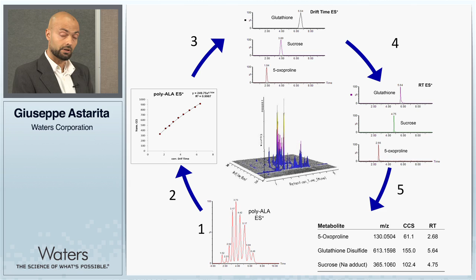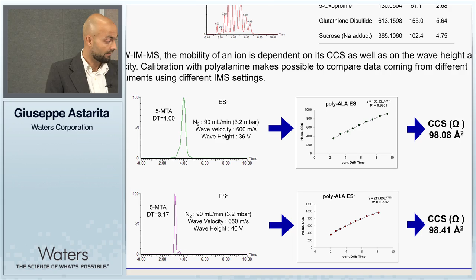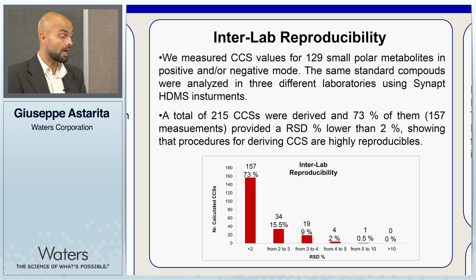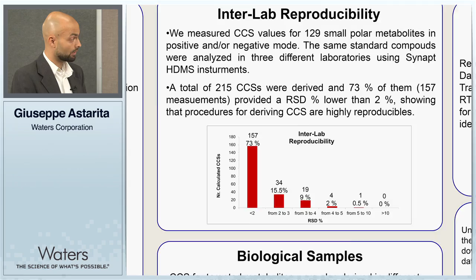The use of a calibration curve allowed us to use different settings for ion mobility for collision cross-section calculation. In this example, we show that we could use different wave velocity and wave heights to obtain 2 different drift times for the same metabolites, which, however, after the calibration curve, led to very similar collision cross-section values. Again, the use of calibration with polyalanine allowed us to use different instruments based in different laboratories. As you can see in the panel, interlab reproducibility shows that 73% of the calculated collision cross-sections had lower than 2% standard deviation, while other 15% had a standard deviation between 2 and 3%, indicating a very high reproducibility in the measurement of collision cross-section.